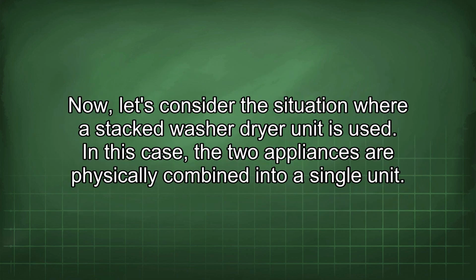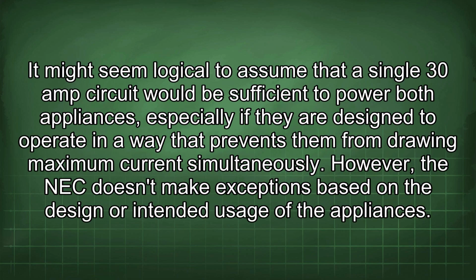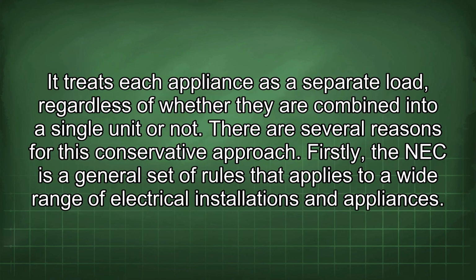Now let's consider the situation where a stacked washer-dryer unit is used. In this case, the two appliances are physically combined into a single unit. It might seem logical to assume that a single 30-amp circuit would be sufficient to power both appliances, especially if they are designed to operate in a way that prevents them from drawing maximum current simultaneously. However, the NEC doesn't make exceptions based on the design or intended usage of the appliances. It treats each appliance as a separate load, regardless of whether they are combined into a single unit or not.